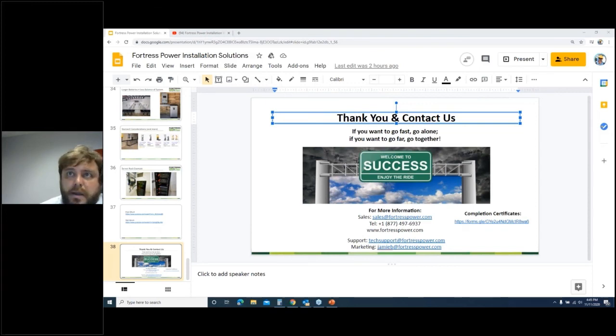So Pete, that's a great point. You do want lithium ion batteries to cycle periodically. You don't want lithium ion batteries just to sit there and discharge. So they will last longer if you are cycling them periodically. Now, if you're cycling them frequently, they're going to last shorter. But compared to a daily full cycle versus just sitting there not being used for 10 years, the full cycle battery, granted, we have a 6,000 cycle warranty, or 10 years, whichever comes first. So if you're cycling it once a day for 10 years, the 10-year mark will come first, and your battery will last much more healthy.